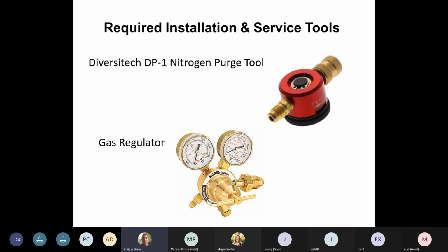A couple other tools nice to have. Nitrogen purge tool. It hooks up to your nitrogen tank. It has two settings. It has purge and it has like a weld setting. So once you put it to that weld setting, it will only allow enough nitrogen to go through your lines. So when you're doing your brazing, we want nitrogen going through our lines because we want to get the crap that's inside that lines not to form. If you're not running the nitrogen through and you're welding your line, it will make little flakes inside the copper. Those little flakes are going to go into your TX valve. They're going to go into your strainers on your mini split.